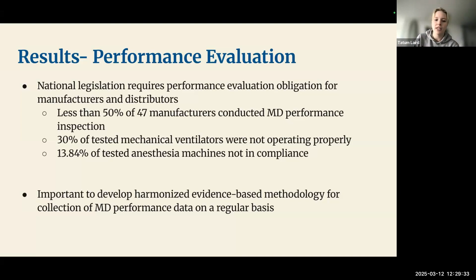And 30% of the tested mechanical ventilators were not operating properly. These are just some statistics that they found. And 13.84% of tested anesthesia machines were not in compliance with the regulations that the anesthesia machine should have been compliant with. So again, a little bit frightening. It shows that there needs to be strict regulation for performance evaluation. And it's important to develop a harmonized evidence-based methodology for collection of medical device performance data on a regular basis.